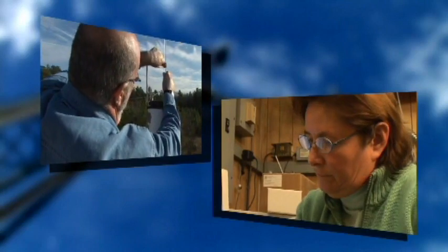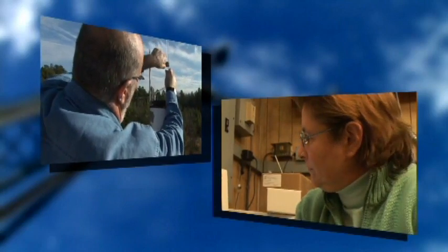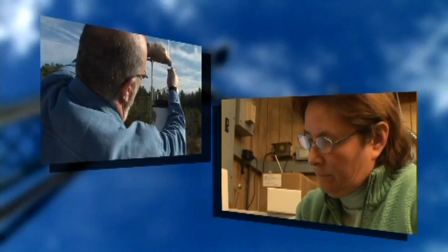Calibration of meteorological systems always takes at least two people to perform. The reason is simple. While one person is performing the test on the instrument, another person must record the responses.